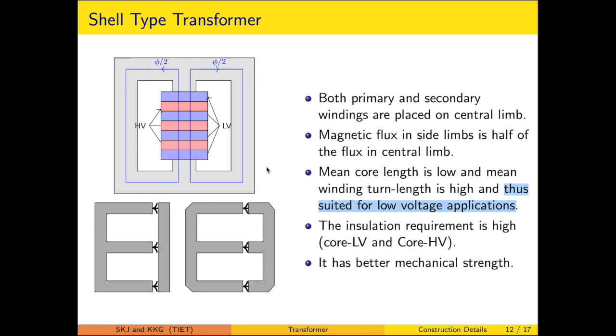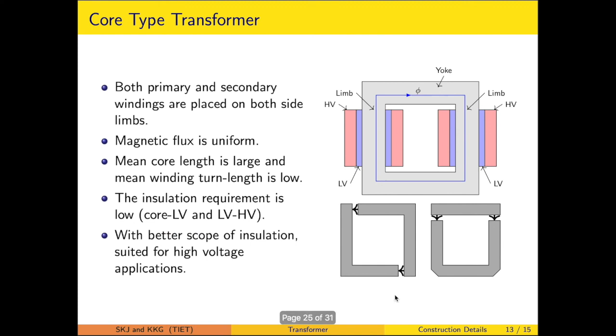Core type structure has a concentric winding, half on one side and half on the other side. However, the same flux is linking the whole of the core, so the magnetic flux in this is uniform. The mean core length is larger because it is to carry the full flux, in comparison to the shell type, which was carrying half of the flux on one side. However, the mean winding turn length is low. Because of this concentric nature of the winding, the insulation requirement is low. Because of the better scope of insulation, this is suited for high voltage applications.